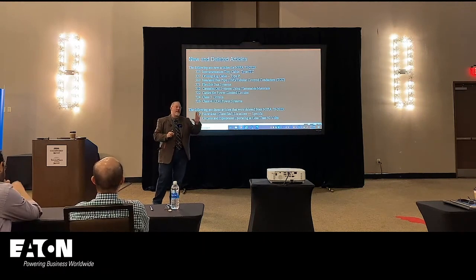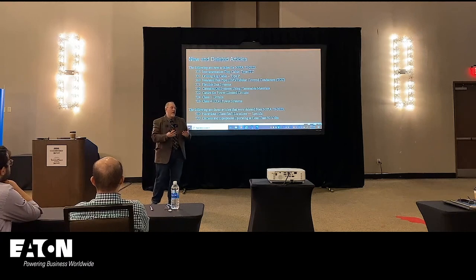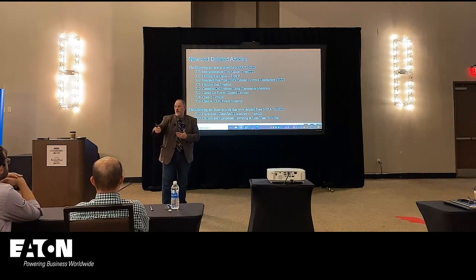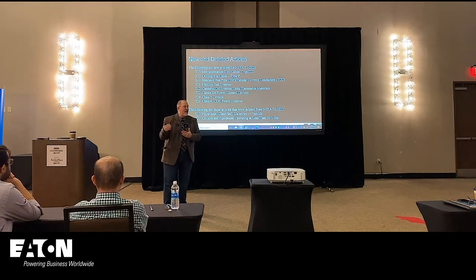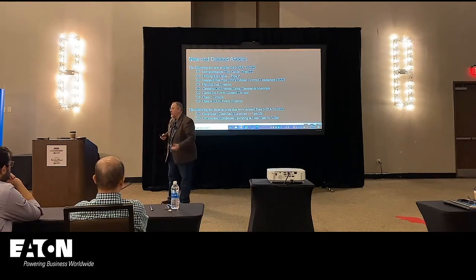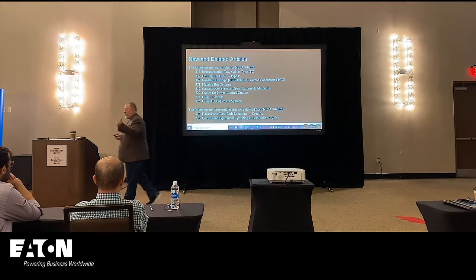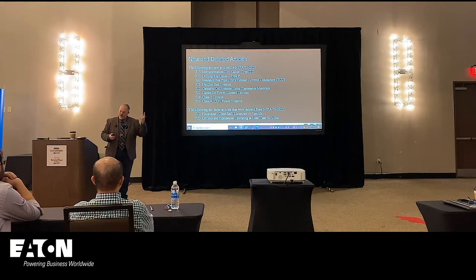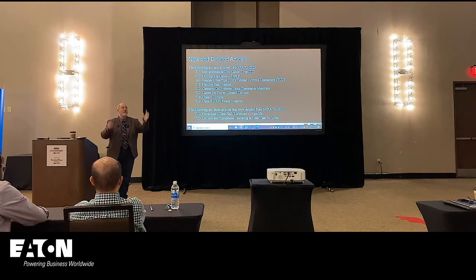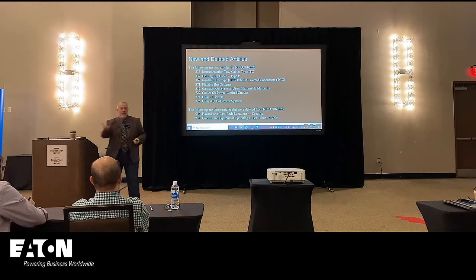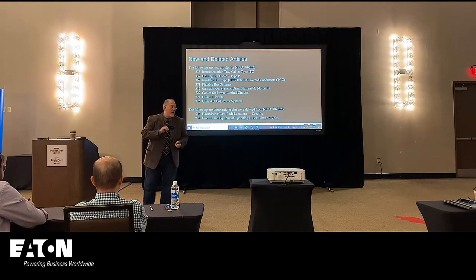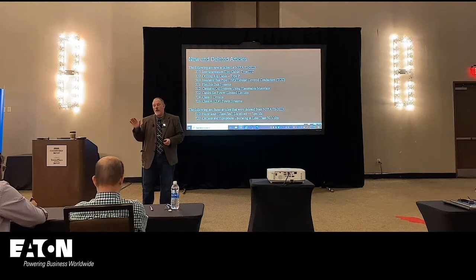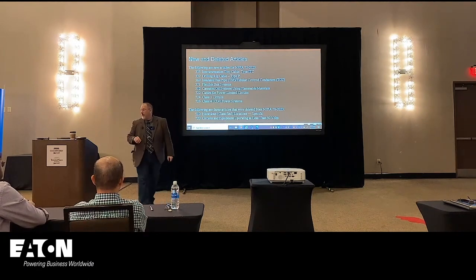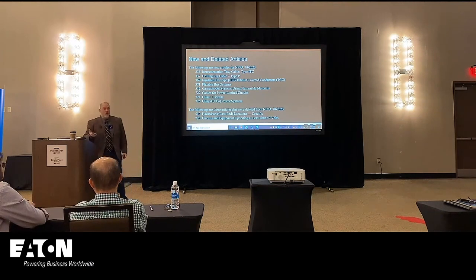So UL got a whiff of that, and the industry got a whiff of this, and they said, we really need to formalize this, because if it is a good technology coming to the market, we don't want a failure. We don't want to give something a bad flavor if it is a good solution. So UL created a standard for it. They did some research, and we created some requirements and new definitions in the NEC. So take a look at 726 for pulsed power. I think the focus of that technology is around powering LED lights, because it's DC. If you think about it, everything we have that's plugged in has to go through a converter, right? And there's a lot of work going on in low voltage DC distribution in the code and in standards. So it's another thing to keep your eye on with regard to application of power distribution and how it may change in the future.